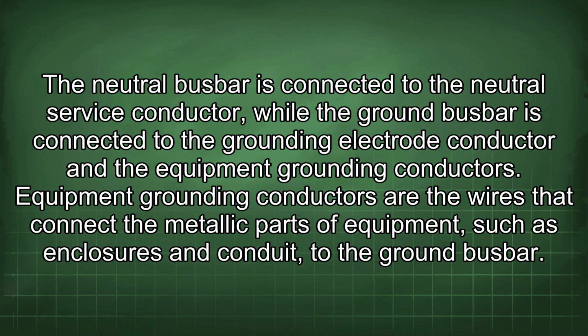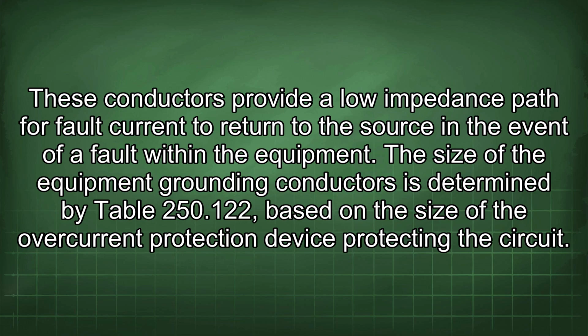Equipment grounding conductors are the wires that connect the metallic parts of equipment, such as enclosures and conduit, to the ground bus bar. These conductors provide a low impedance path for fault current to return to the source in the event of a fault within the equipment. The size of the equipment grounding conductors is determined by Table 250.122, based on the size of the overcurrent protection device protecting the circuit.